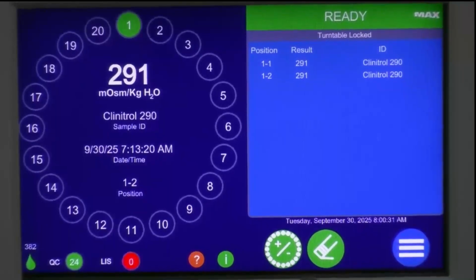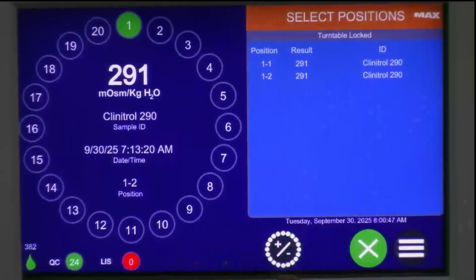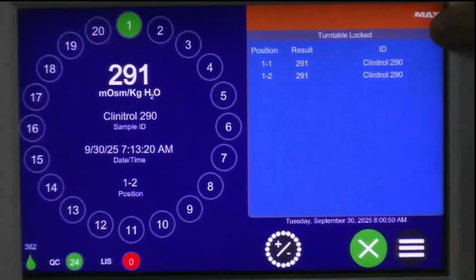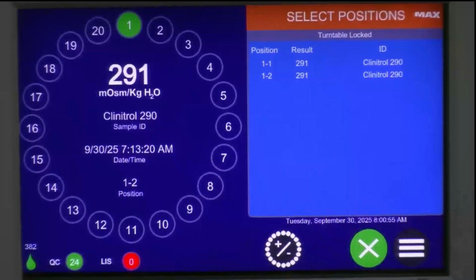So looking really good. This little plus or minus sign right here, this would allow me to add tests to the turntable. So like I was saying before, you don't have to batch test on this. You can continuously add samples to the turntable. So if I wanted to add a test, I would simply just hit this button. Then it would ask me where I want to put the test. As you can see up here on the top right, it's telling me to select a position. I would select the position, and then I would hit play.